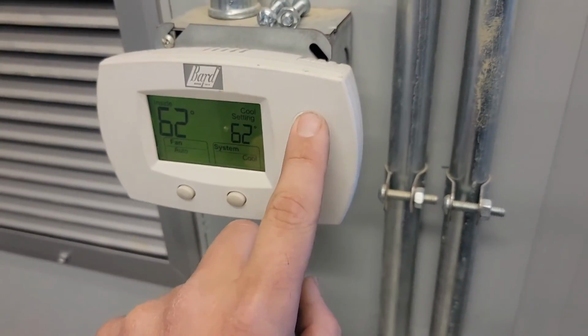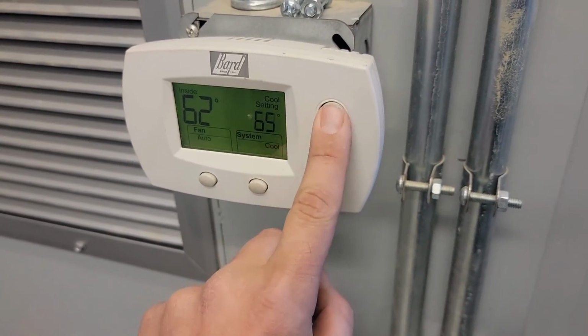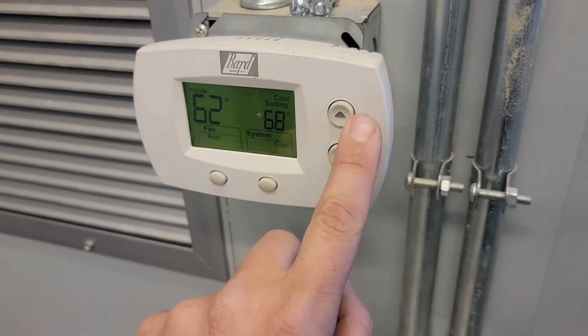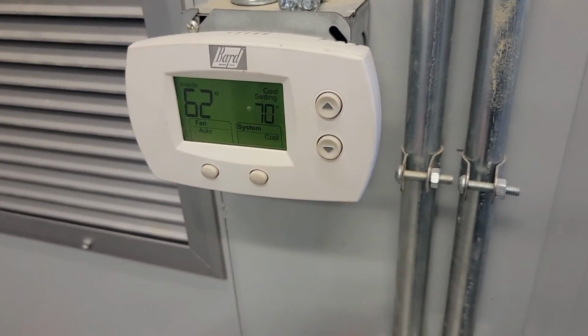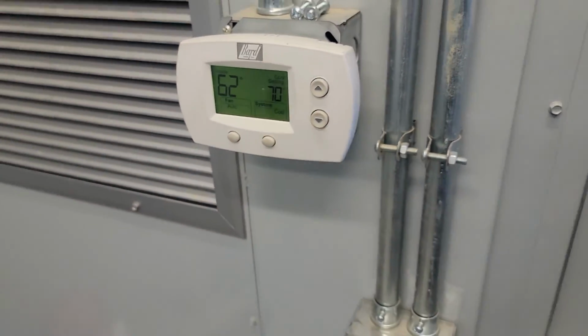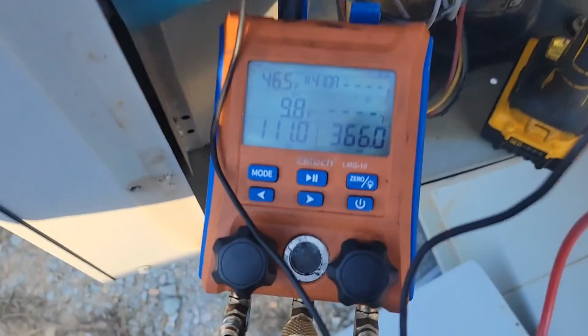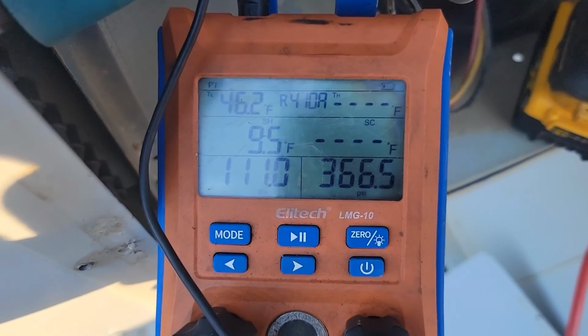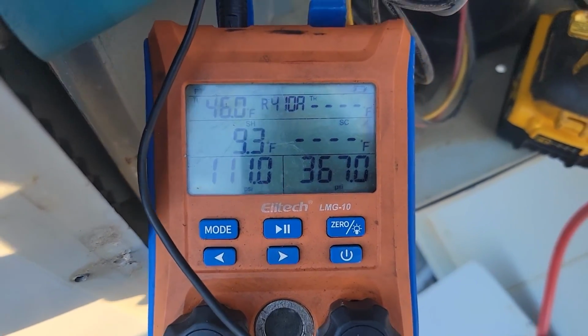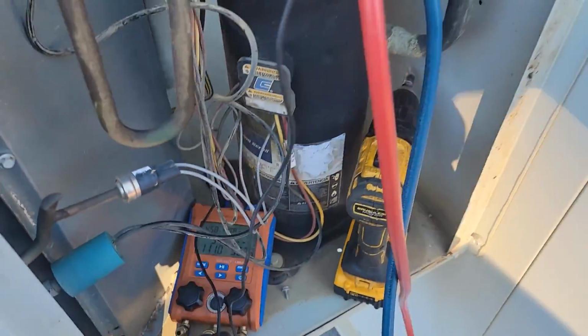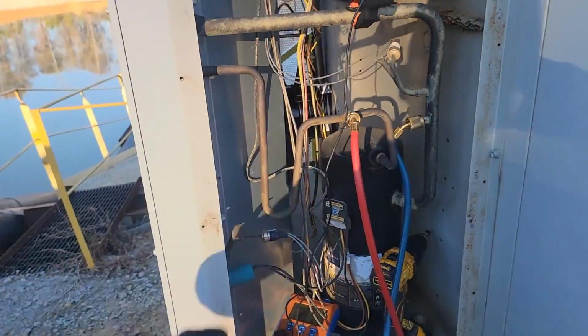That's awesome. Now I'm gonna turn this thermostat back up. That way it doesn't freeze up overnight. About 70, that'll do. Suction line temperature is 46 degrees. Superheat is 9. Man, everything looks great so far. I'm gonna button it back up.